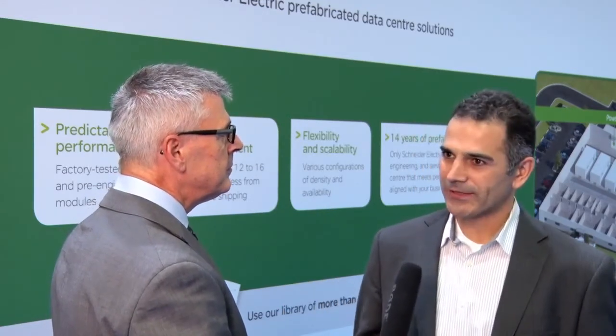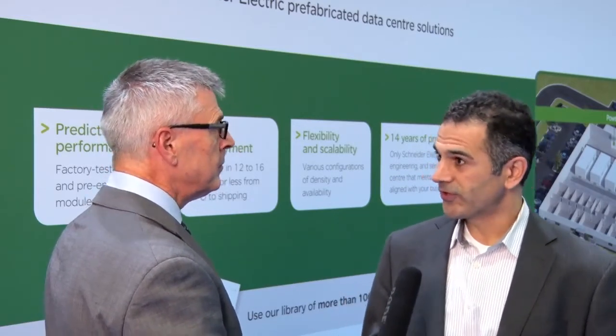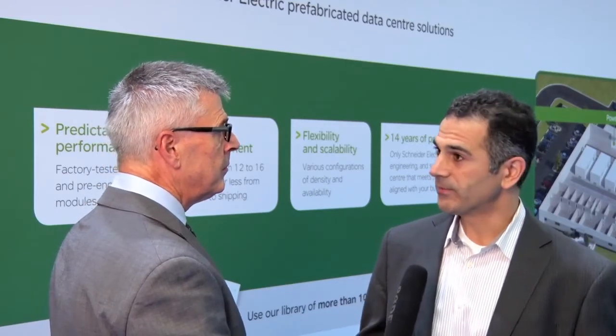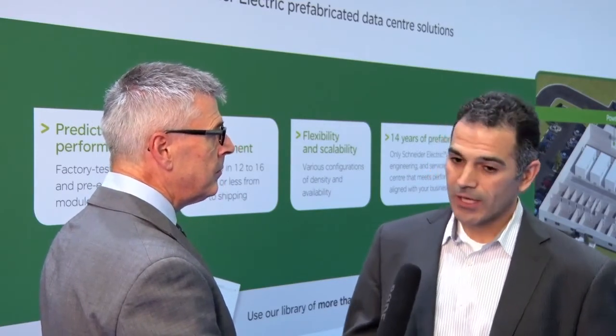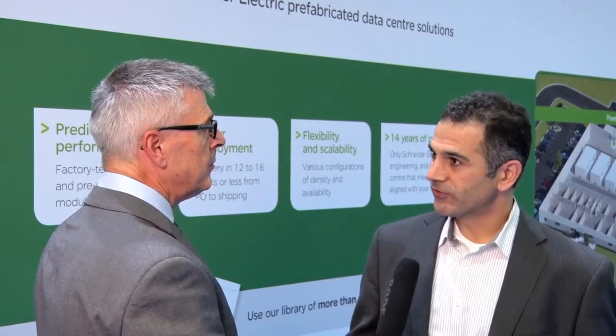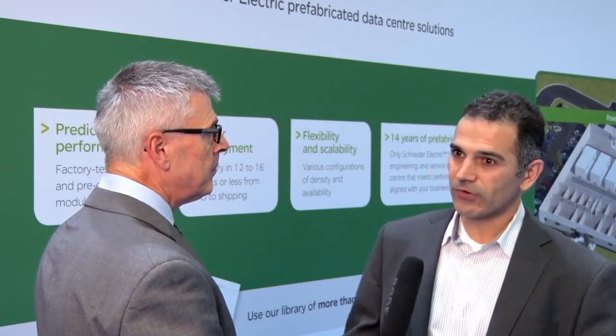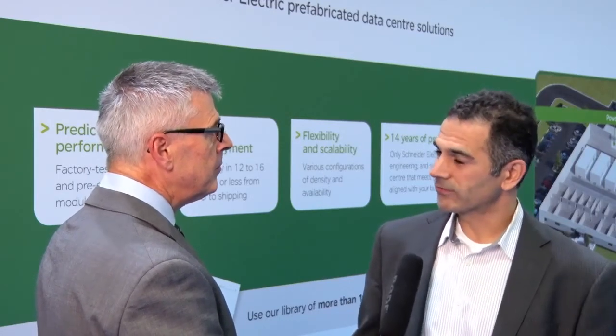One of them is signal reference grids. Back in the day of mainframes, we had these large machines that were connected by RS-232 type cables that were very susceptible to ground noise. So what do you do? You have to have an equipotential plane, and so they'd put these signal reference grids down to have a common zero reference voltage for all of the equipment, and that worked, right?